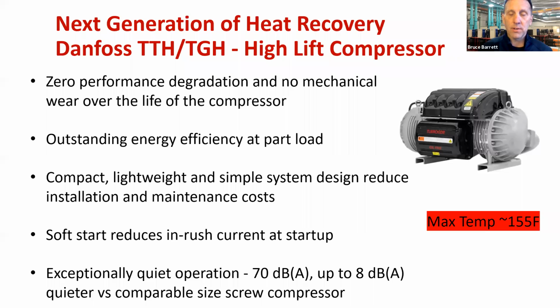So the next progression is carrying this compressor towards heat recovery chillers in a modular format or in a common shell and tube flooded machine, if you will. Still has the soft start, very low inrush, exceptionally quiet operation. And again, no oil to degrade performance over time.